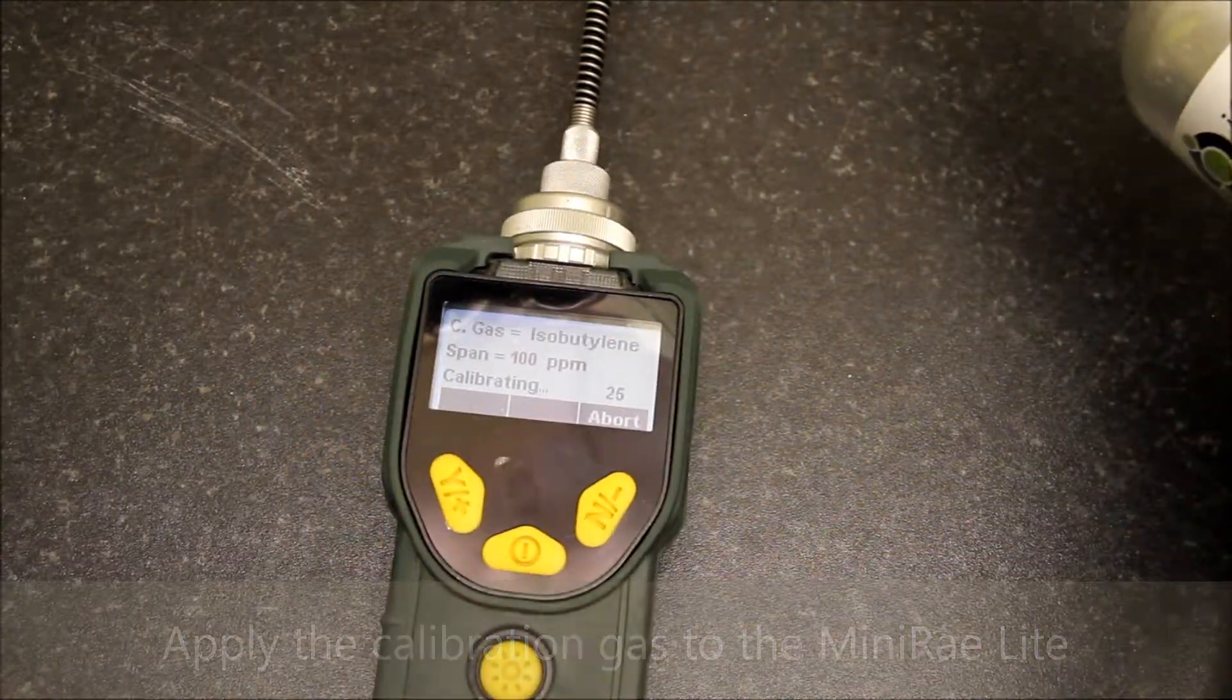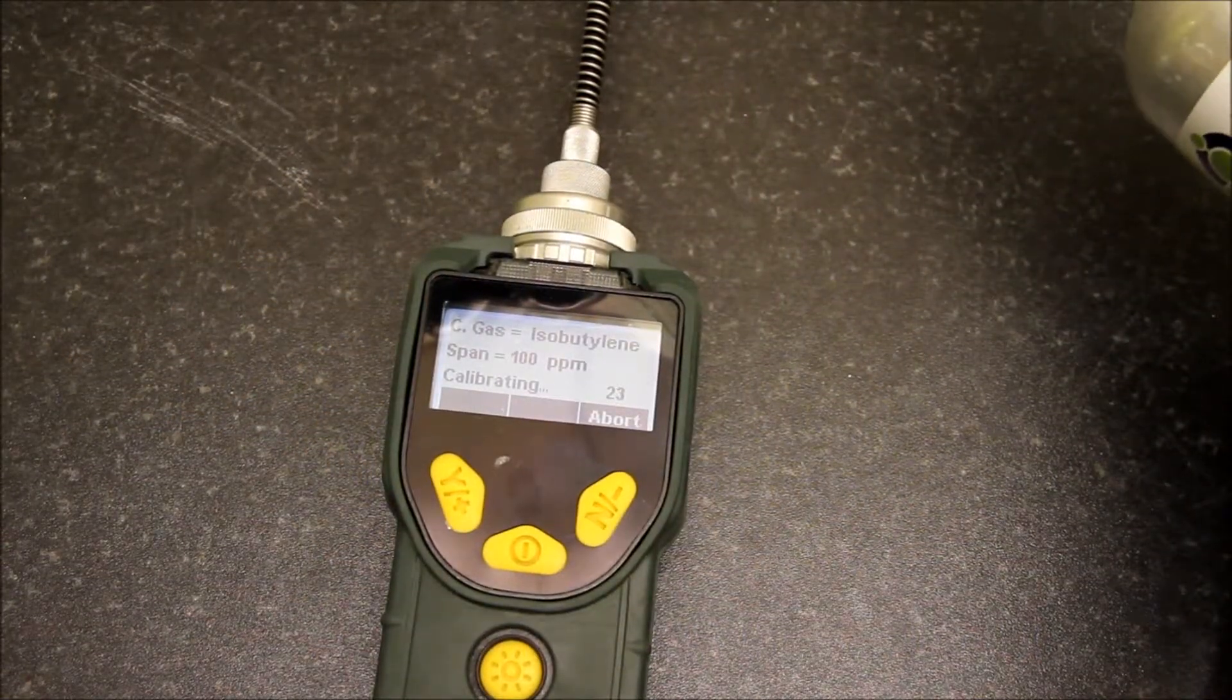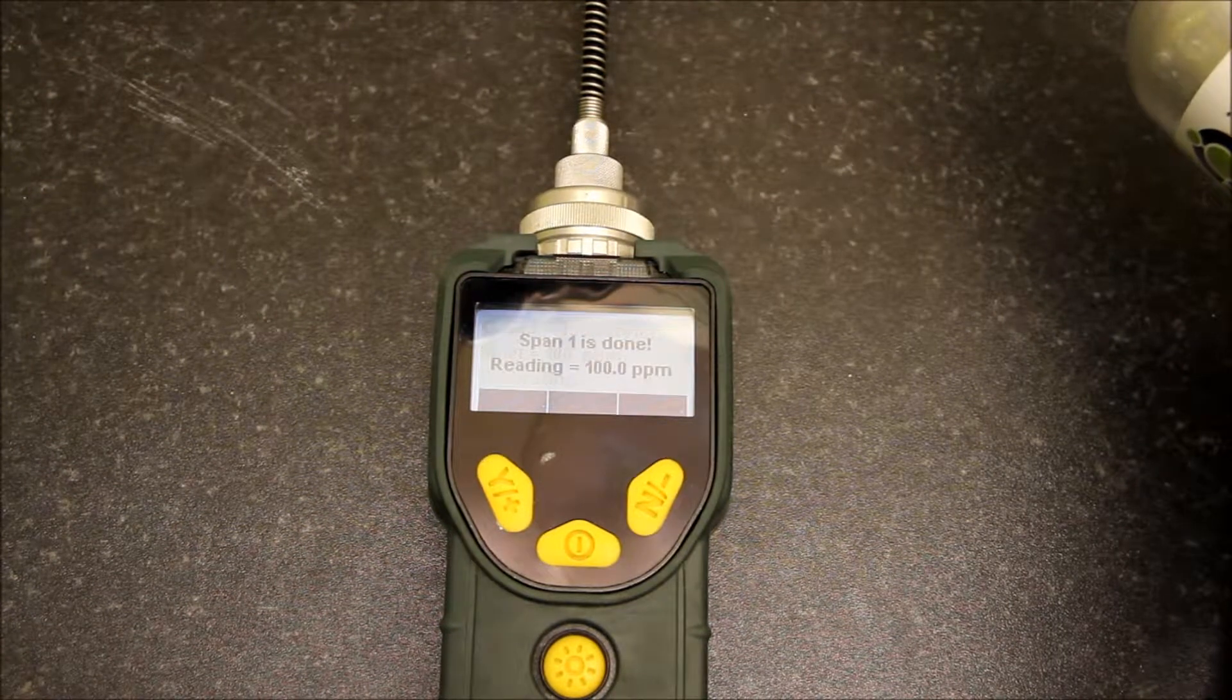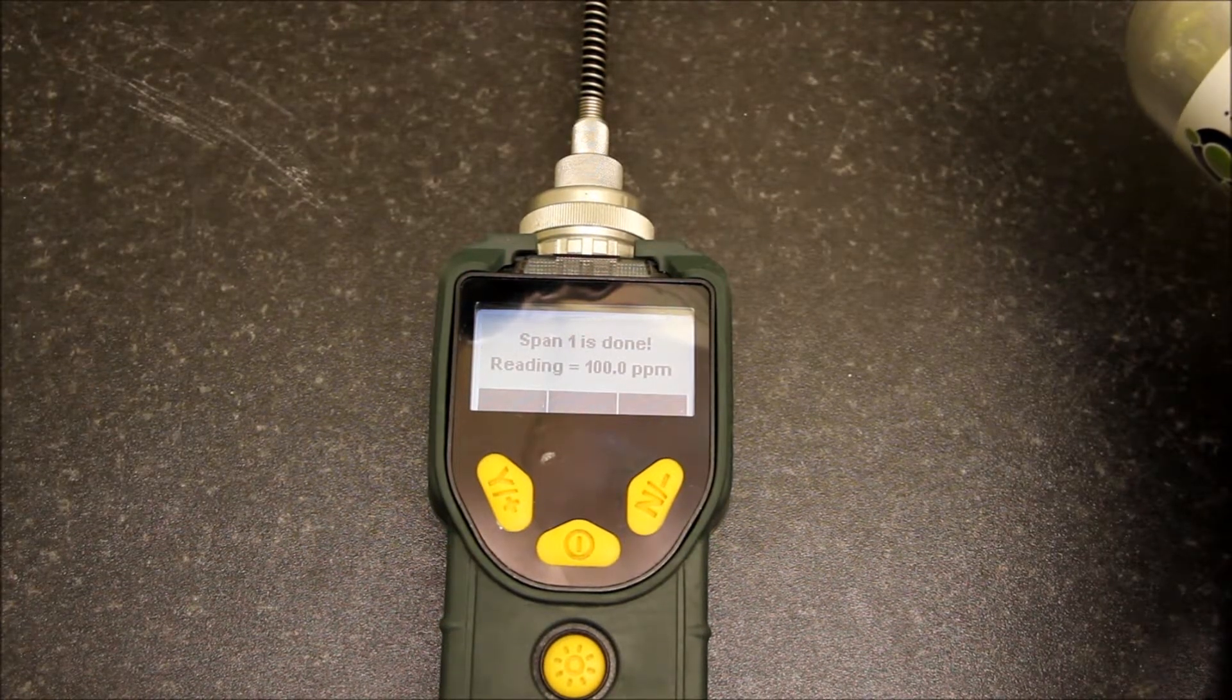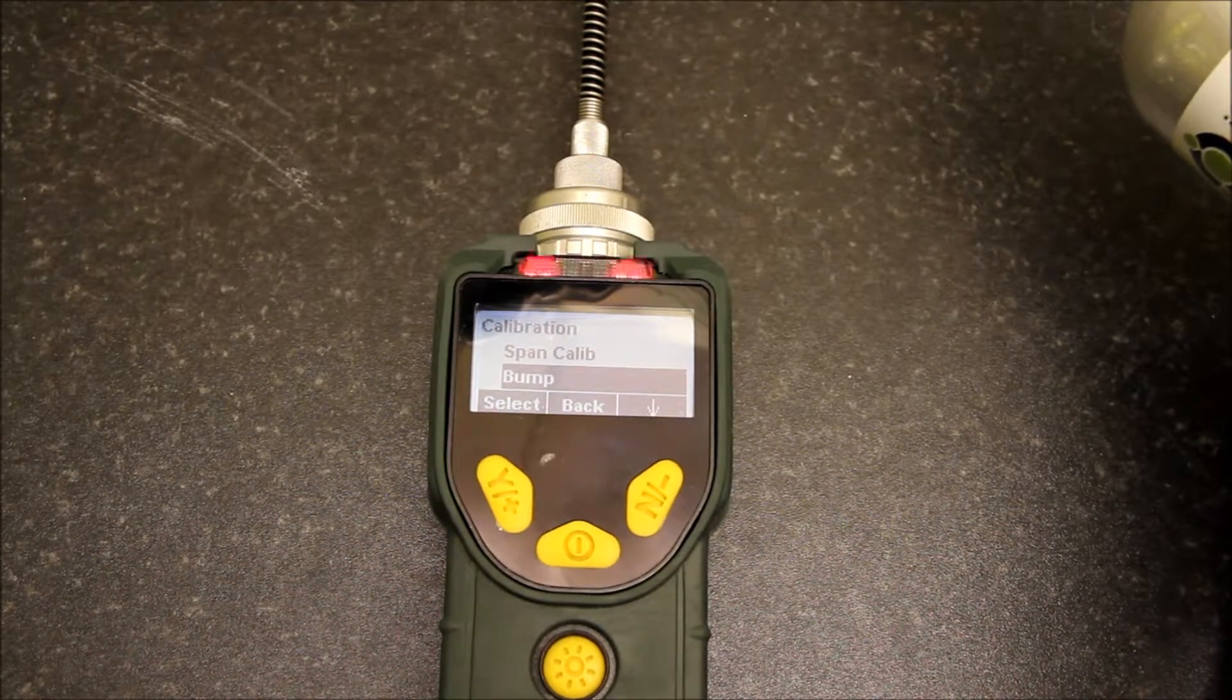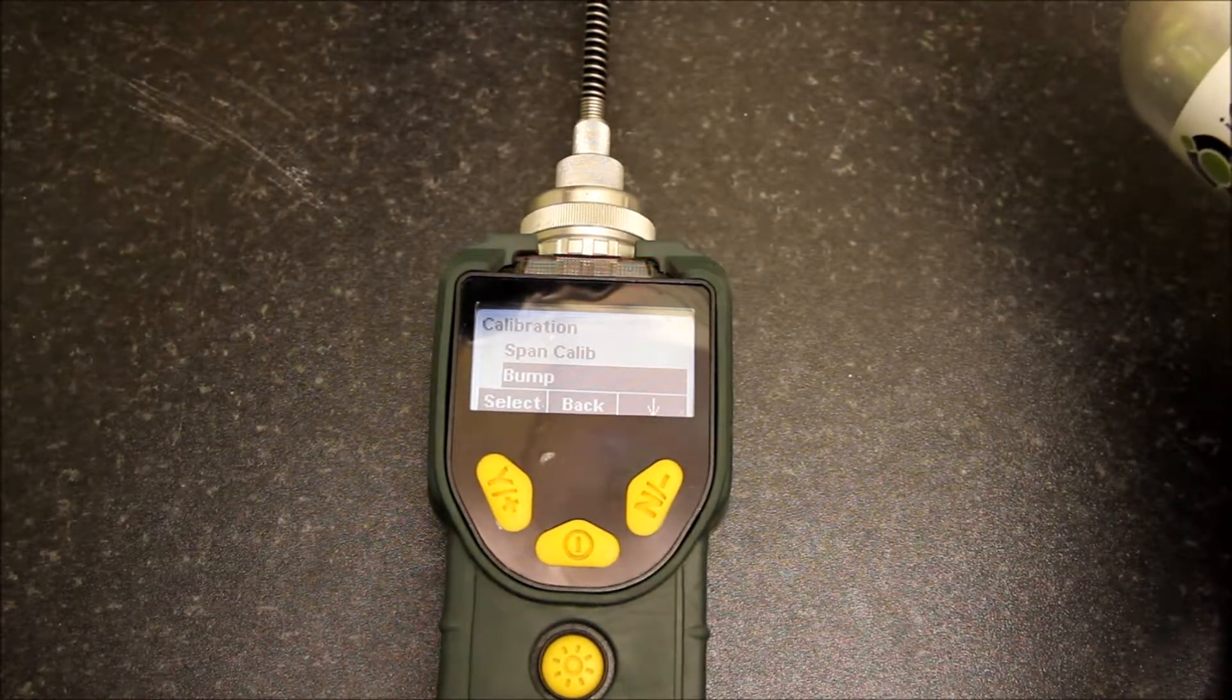You'll see the unit has started to auto calibrate and it will now take 30 seconds to calibrate. We're now entering the last few seconds of the calibration phase. It will now display the live value, which is 100 ppm spot on. We now remove the gas.